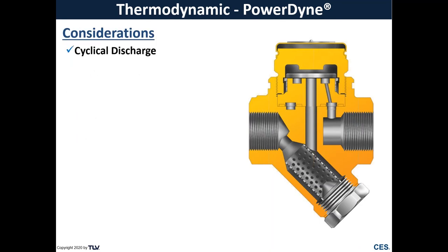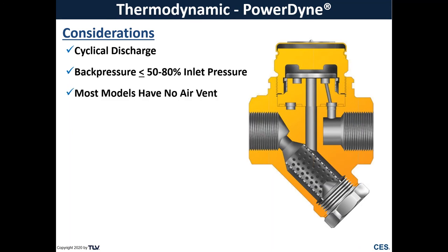Some considerations to think about with this trap is it is a cyclical discharge. That trap needs to open and close, and so every time it's closed, you're going to get a small amount of backup. So you just need to consider that when installing this trap. Because your upstream pressures and downstream pressures are pushing up against your disc, you need to be considerate of your back pressure, because it is limited to between 50 and 80% of your inlet pressure. Most other models, other than TLV disc traps, don't have an added air vent capability. There's no added thermostatic element. And with this trap operating on radiant heat loss from the top side of the disc, this is going to be susceptible to any wind or rain. It's going to cause this trap to cycle more frequently.